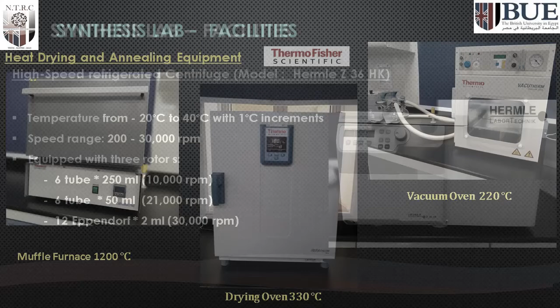The chemistry lab also includes high-speed refrigerated centrifuge with model, Hermle Z36HK. This device is used for separation of our as-prepared nanomaterials. The device has temperature from -20 degrees centigrade to 40 degrees centigrade with 1 degree centigrade increments, speed range of 200 to 30,000 RPM. The centrifuge is equipped with 3 rotors.